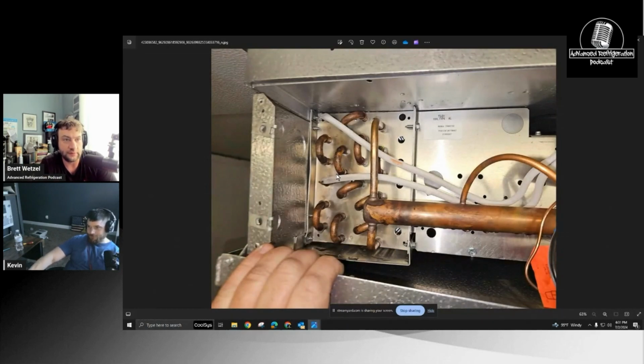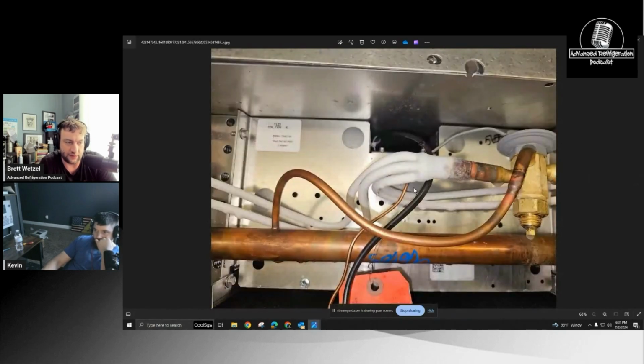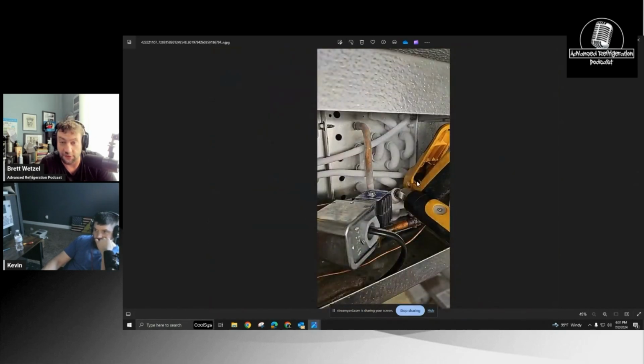Yep, 100%. Which means this doesn't show its head for, I don't know, 3 months, until you have about 4 feet of ice on that side of the coil. So typically I'll do 2 things. One, play with the EPR, and I'll get to that in a second. And the other thing is I put the defrost termination on this side, because no matter what, you're always still going to get frost on this side. So if someone messes up the program that you just made changes on, at least the defrost termination sensor will still be sensing the side of the coil where it gets all the ice all the time.